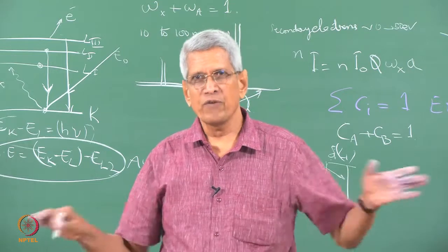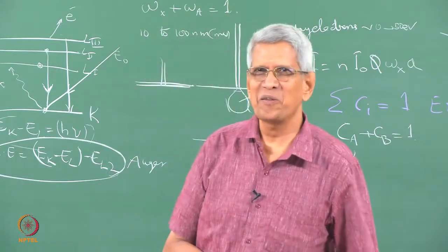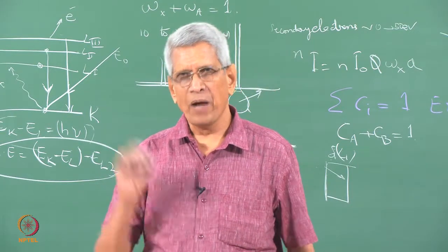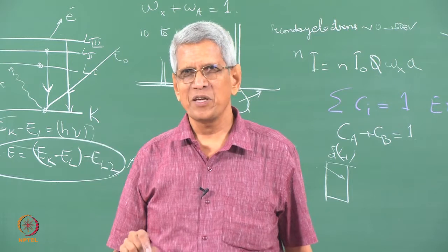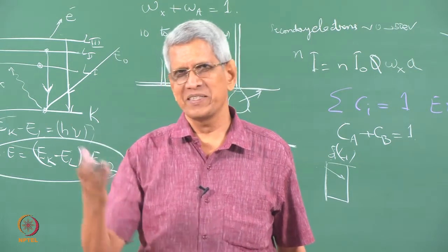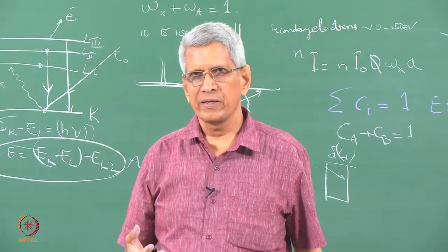Then the energy resolution is essentially determined by the detector, over which we have no control. So we have to accept that if we want a better energy resolution, we have to go for, as I mentioned, the bolometer. The problem of a bolometer is that it has to operate at microkelvin temperatures, that is the only problem. Whereas SDD detectors, even with Peltier cooling, can be operated; you do not require liquid nitrogen cooling of the detectors.